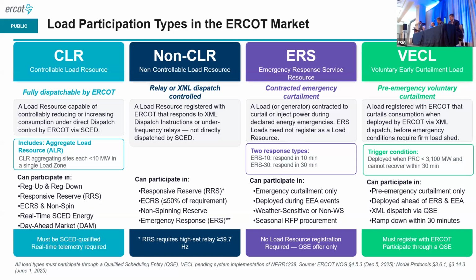But a non-CLR, an NCLR, can participate in ancillary services as well. Typically what we see NCLRs provide is more frequency-based response through use of a high-set under-frequency relay, looking for low frequency events and responding very rapidly by disconnecting.